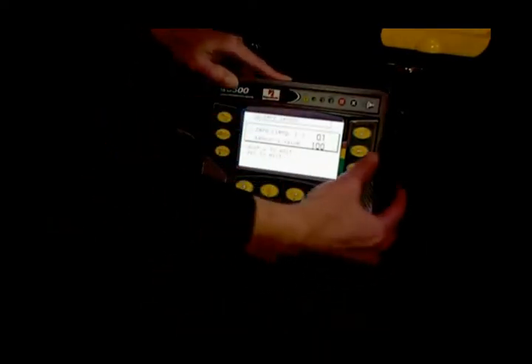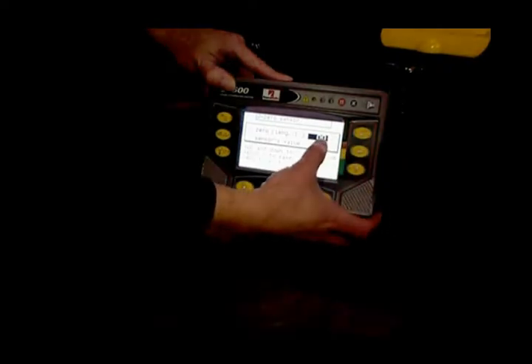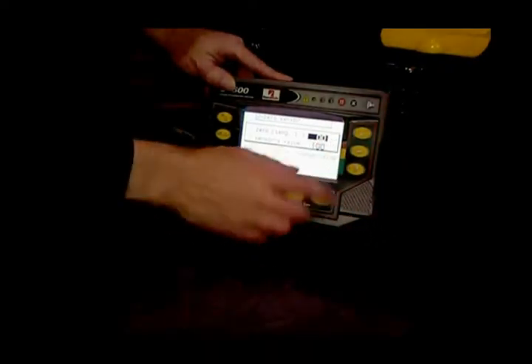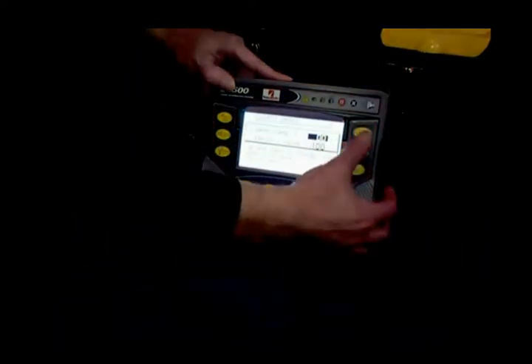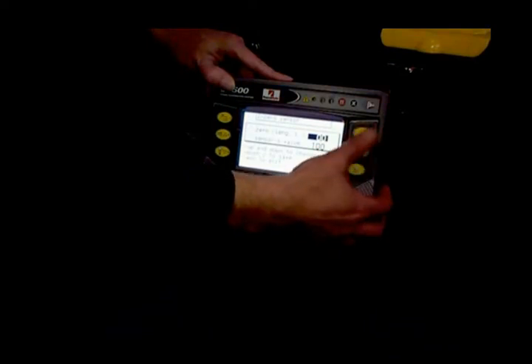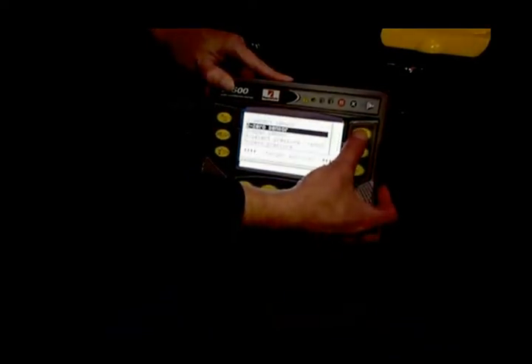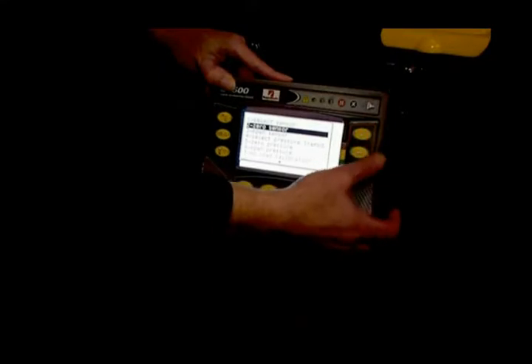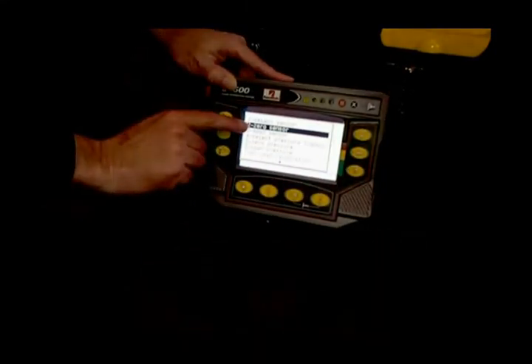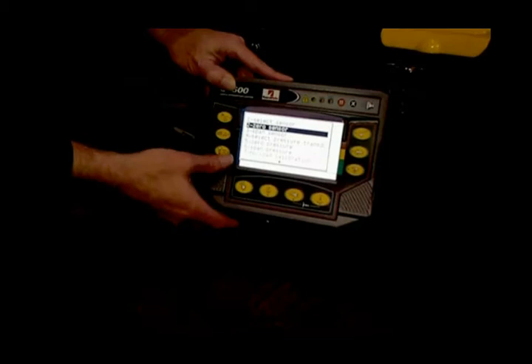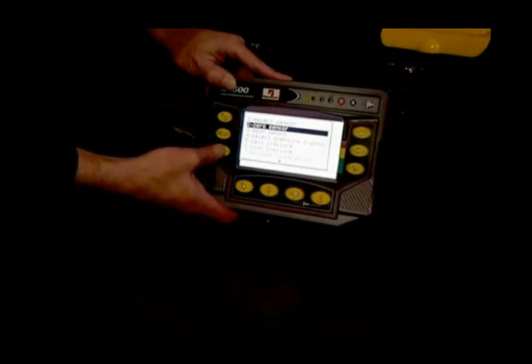So what you would do here is simply press the check mark to highlight it, and we want this to be at 0. So you would simply hit the check mark again, and it would save the value. And that's all you do for zeroing the sensor. The next thing you would want to do is span the sensor.